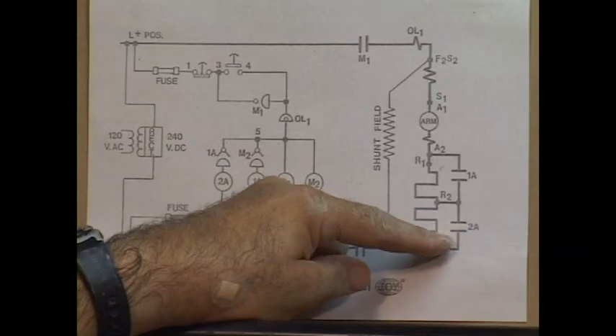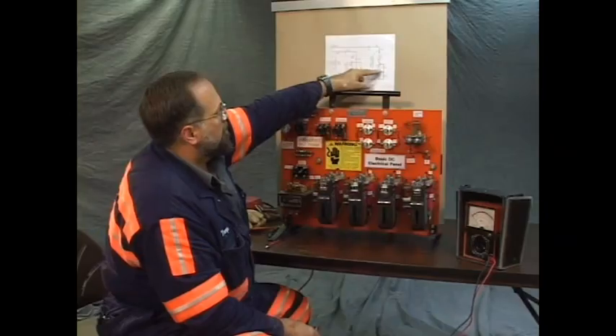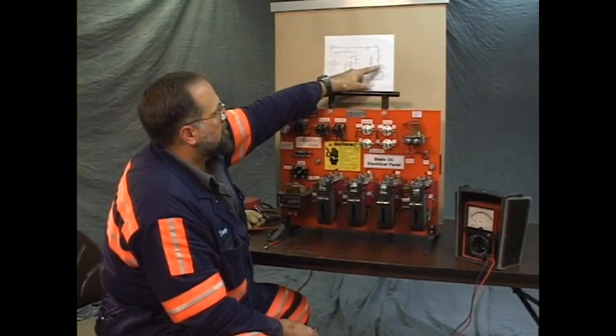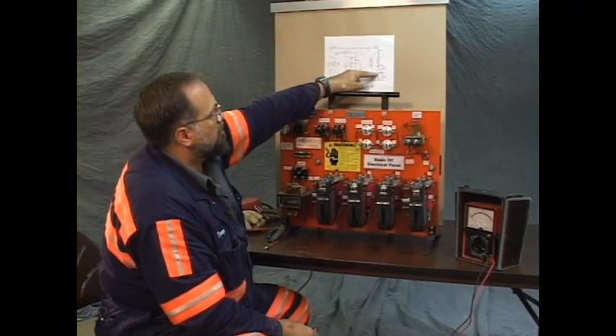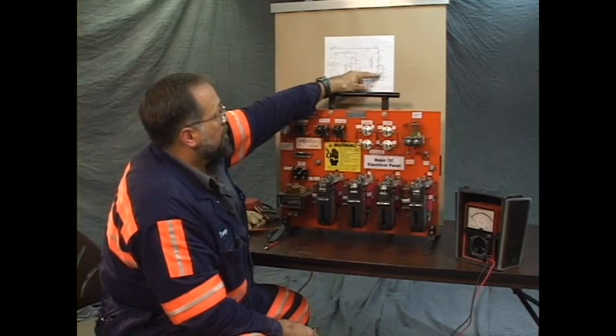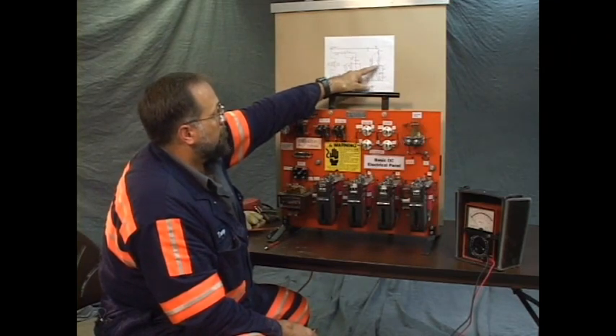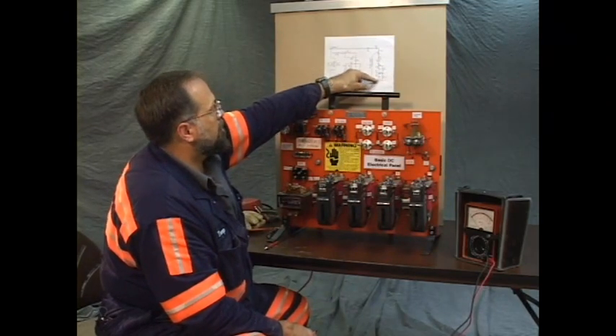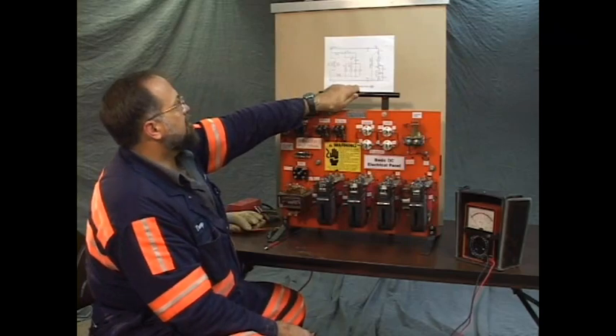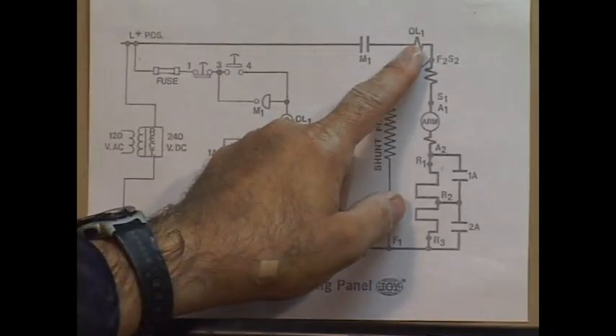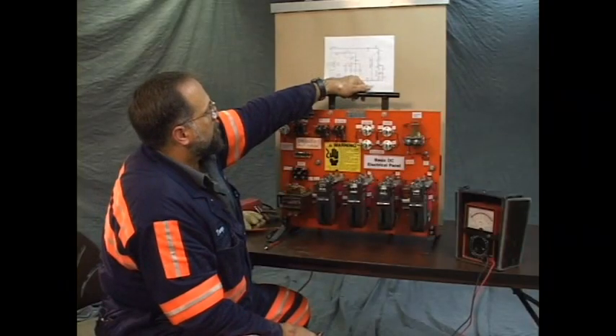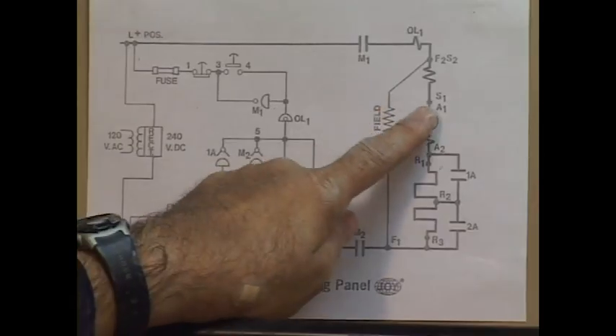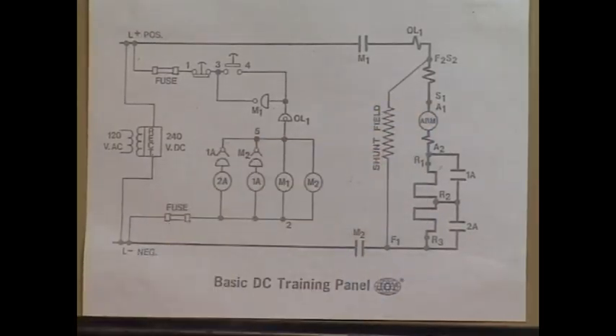If the problem were in the resistance, when the 1A contactor closes, it takes away this portion of the resistor. This to here is gone. When 2A closes, it takes away this portion. And the problem still existed after these two contactors closed, so we're fairly sure it's not here. Let's begin our testing starting at OL1, and we're going to test from OL1 through the armature portion of the circuit.